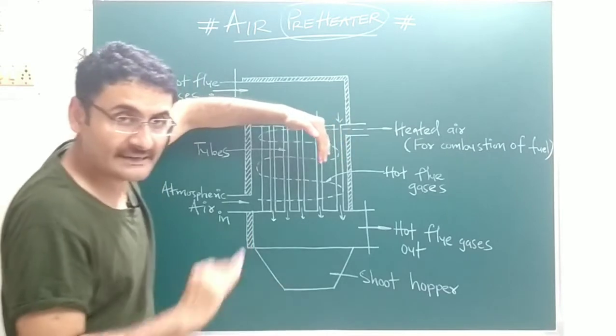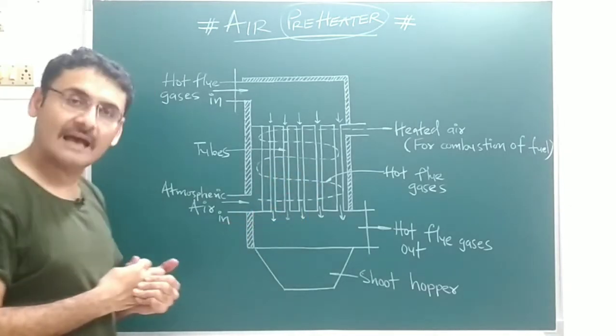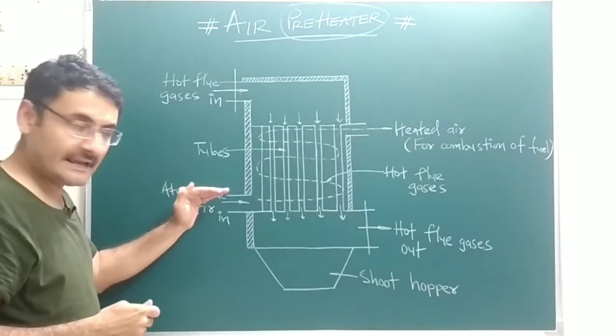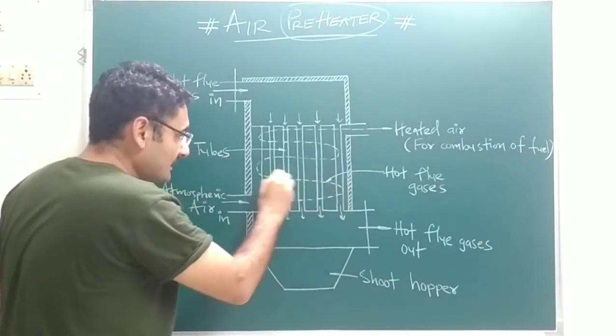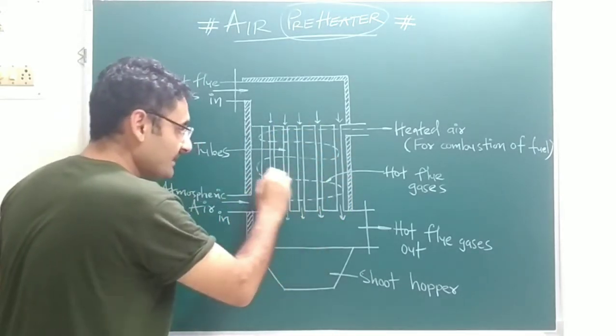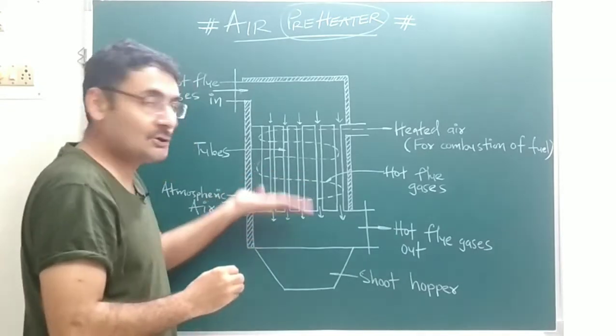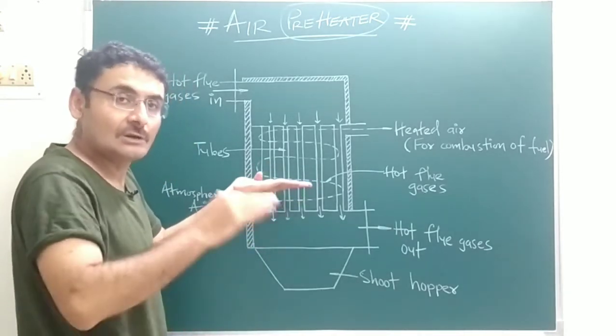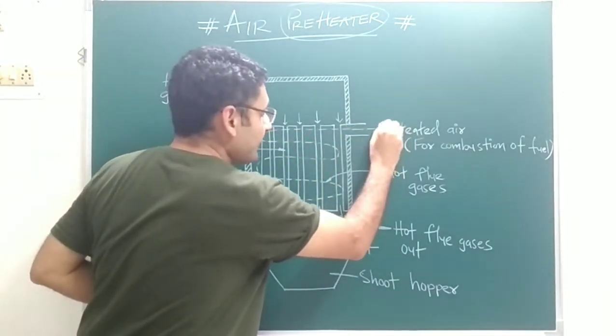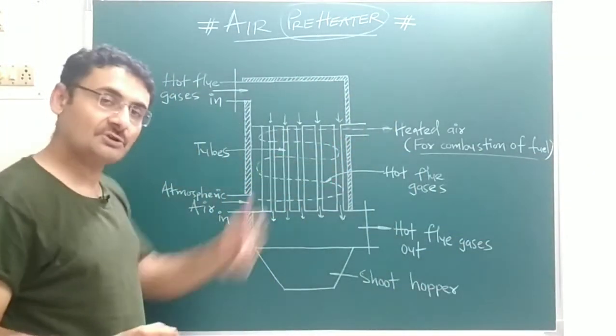These pipes become heated. Inside the air preheater, heated pipes are present whose temperature is high. From the bottom side of the air preheater, atmospheric air is taken and passed over the heated tubes. The heated tubes reject their heat to the atmospheric air, so that air becomes hot. Since hot air has low density, it moves upward and we take the heated air from the outlet. That heated air is then supplied for the combustion of the fuel.